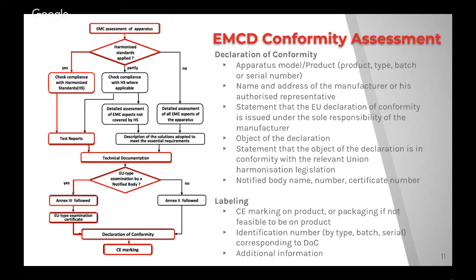Moving on to labeling and the CE marking. The CE marking, as we mentioned earlier, is an indicator of the product's compliance with the EU health, safety, and environmental requirements, directives, and regulations, but it is not sufficient proof. There are no specific color requirements for the letters or the background. In other words, it's not required to print the letters CE in black against a white background. But it should definitely be clearly legible, and the CE logo should be clearly visible. The vertical dimension should be no less than 5 millimeters. Additional information, identification number, batch, or serial number, etc., corresponding to the declaration of conformity is required, and other information such as contact information and the use and installation disclaimers should also be included with the product.